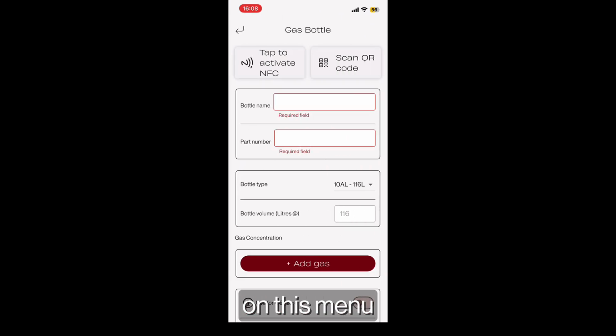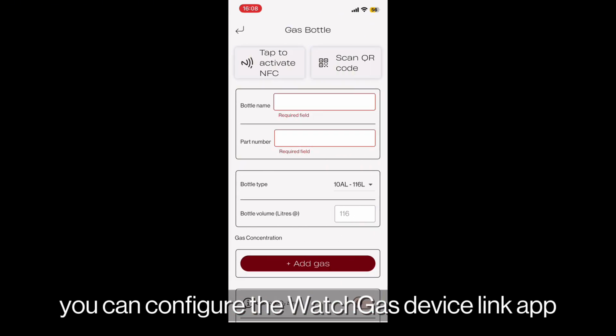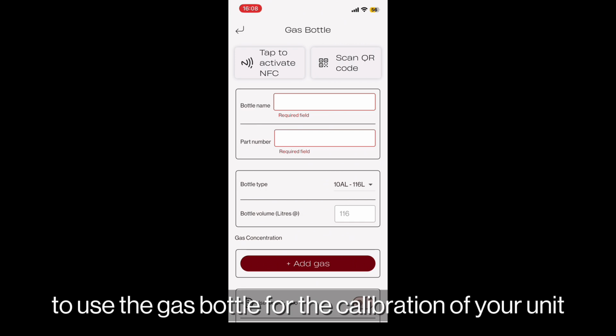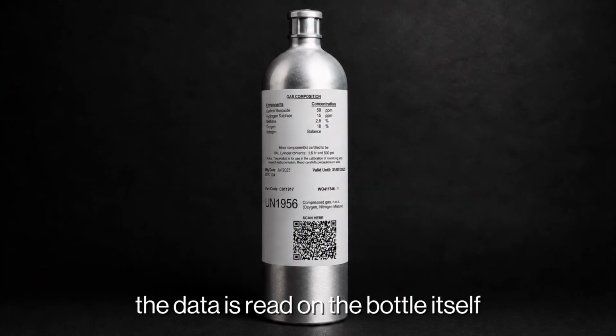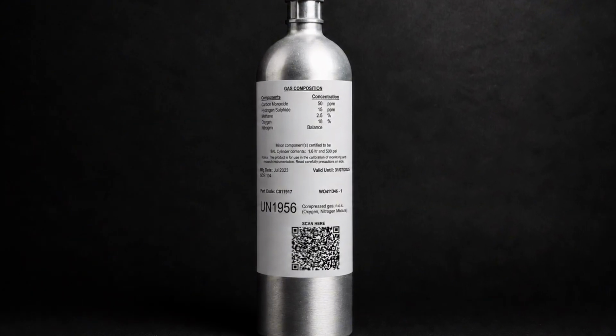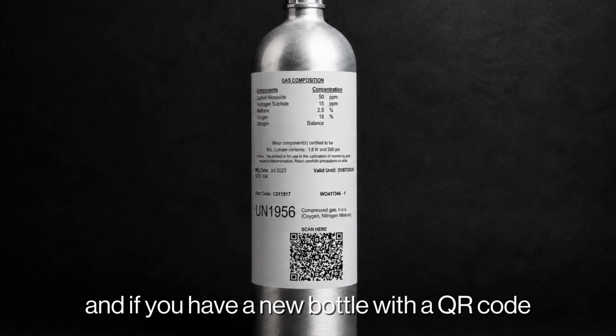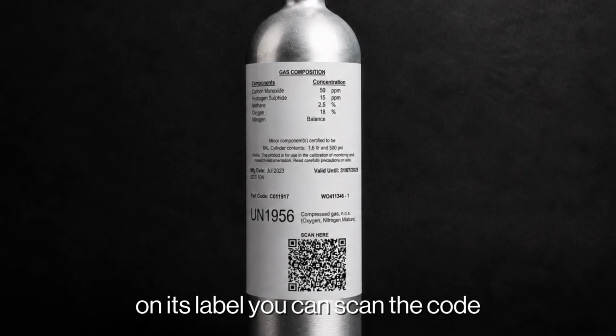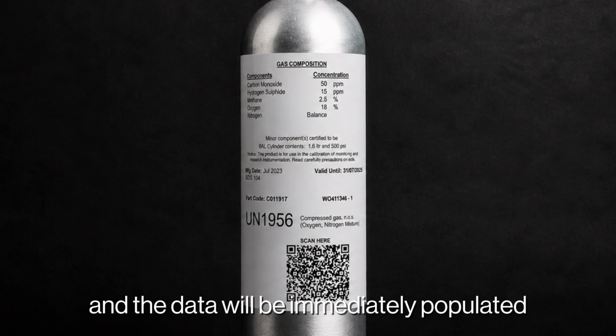On this menu, you can configure the WatchGas device link app to use the gas bottle for the calibration of your unit. The data is read on the bottle itself, and if you have a new bottle with a QR code on its label, you can scan the code and the data will be immediately populated.